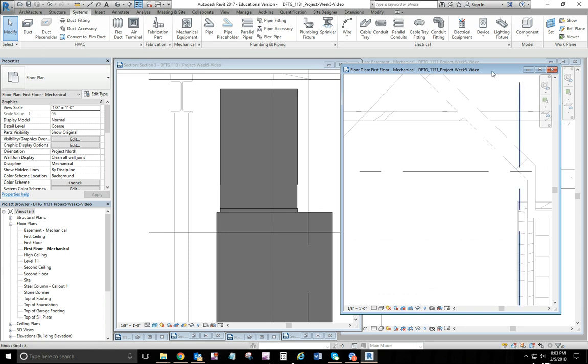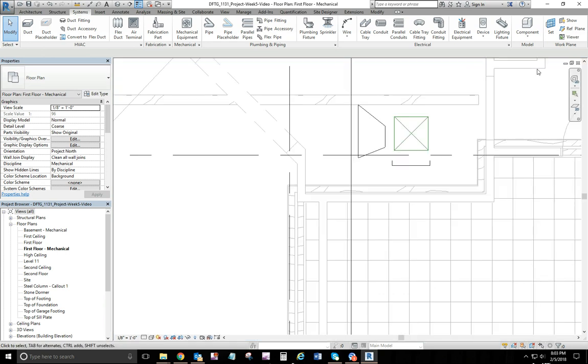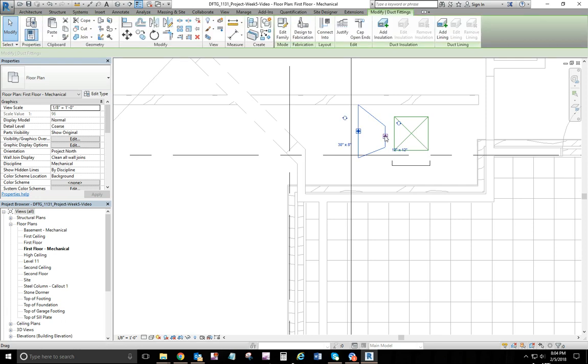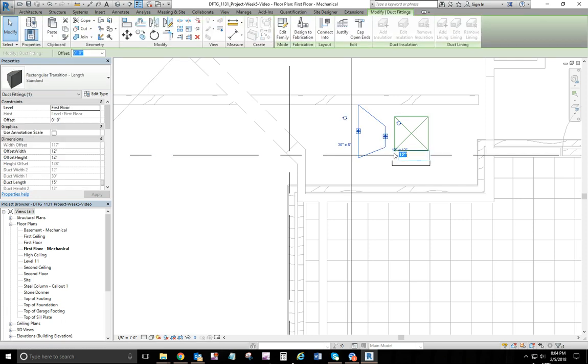Okay, what I did, this is just something to keep in mind when you've got a volume of air going through a ductwork, the cross-sectional area needs to stay the same. So an 8 by 30, multiply that, 8 times 30 gives you so many square inches. And the widest I could be here was 19, so I divided it by 19 inches, and that gave me 19 by 13.